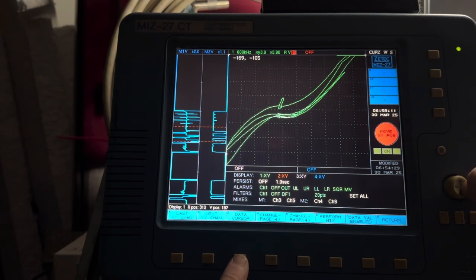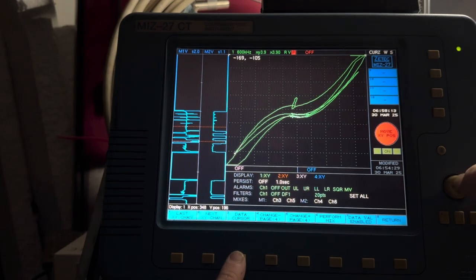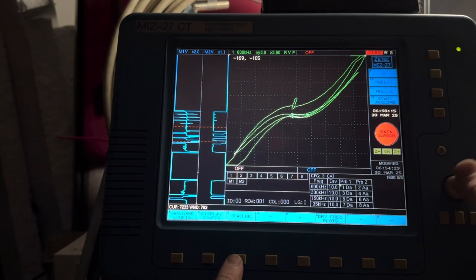Now we got some big signals there. Why are they so much bigger than the flat bottom holes? Well, that's because a 1-inch wide wear scar that's 20% deep has a lot of metal missing relative to the size of the pits.